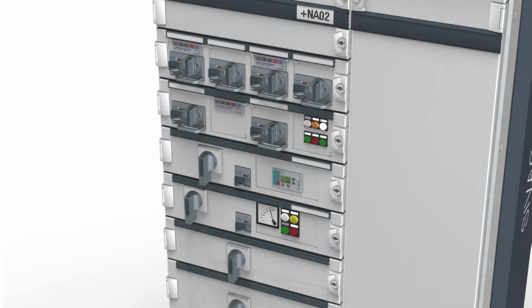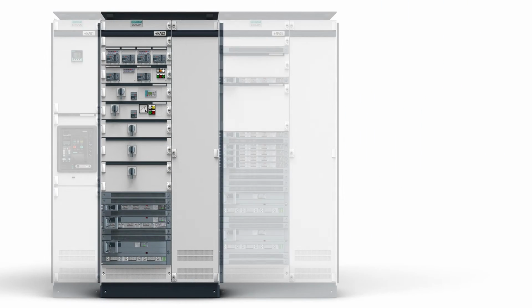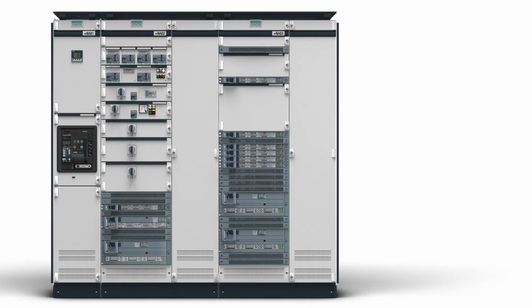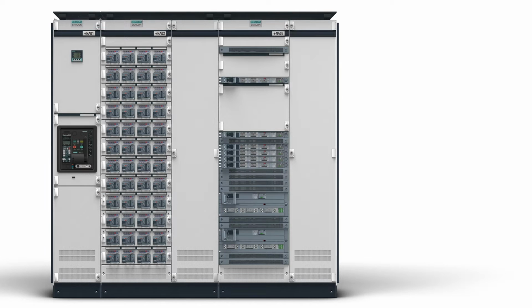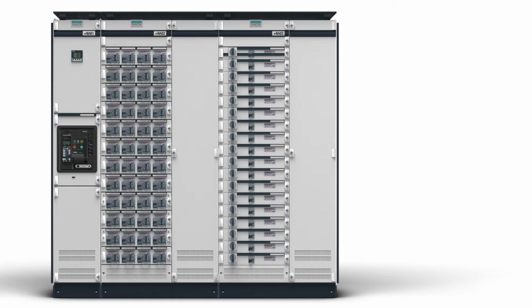The maximum packing density with miniature withdrawable units for outgoing motor and cable feeders amounts to 48 withdrawable units. With the exclusive use of standard withdrawable units for outgoing feeders, up to 18 withdrawable units can be installed in one section.